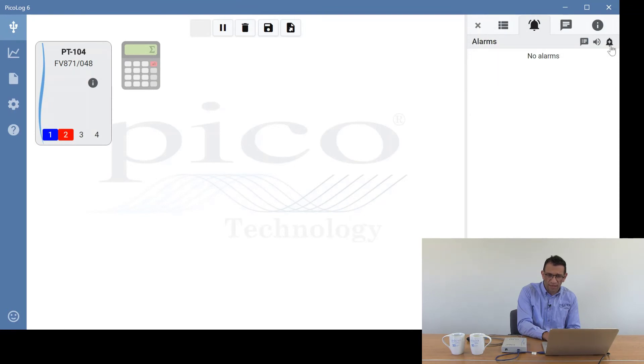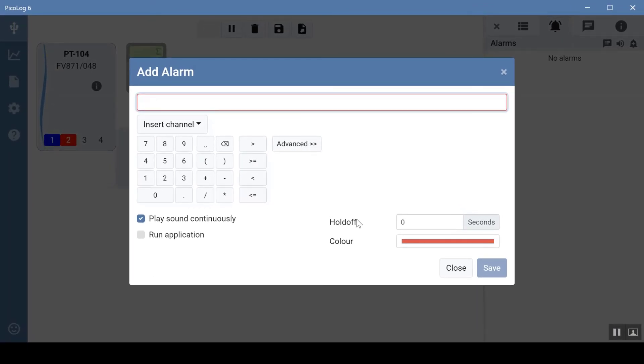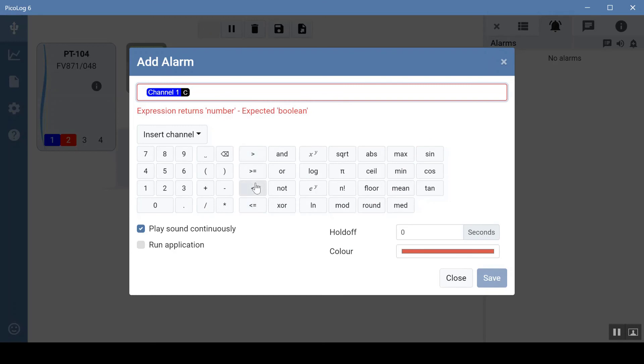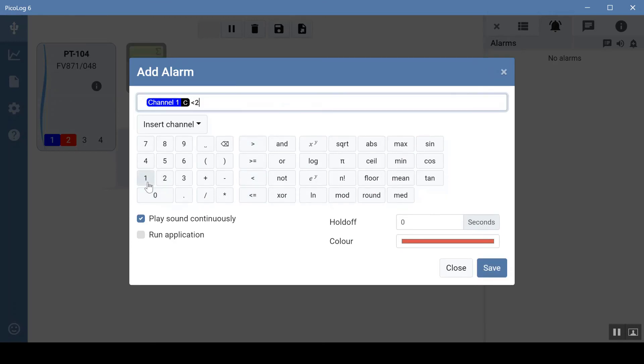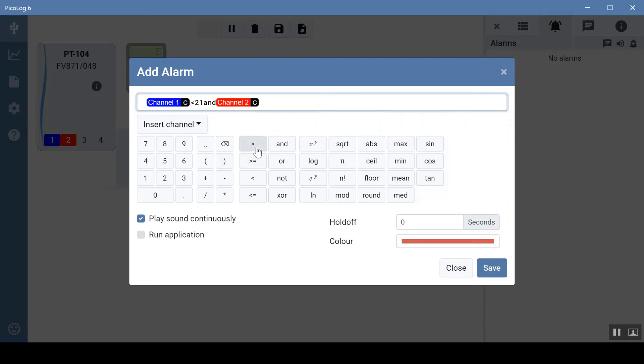The last alarm type is custom expressions. Going to alarms, add alarm, and selecting custom expression — this requires a boolean output, i.e. true or false, which you can define with a combination of various functions found on our website. Clicking advanced opens up all the options. In this case we'll use two channels: channel one and channel two. We want channel one to be below 21 degrees Celsius and channel two to be above 30 degrees Celsius.